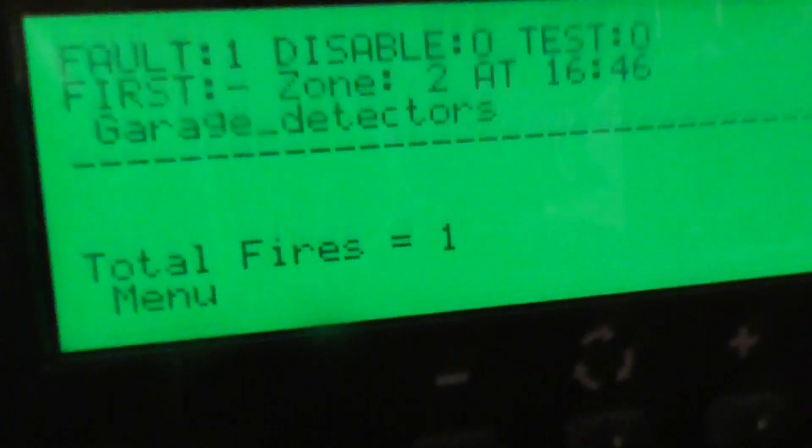So there we go, zone 2 garage detectors. I'll silence it for a bit and we'll test the call points.